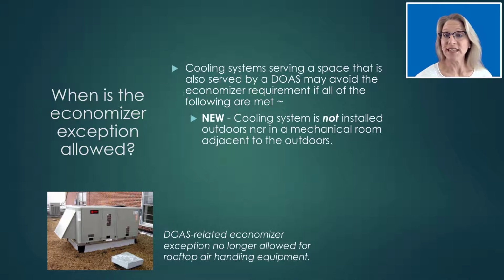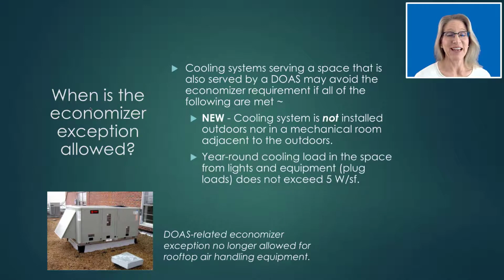The 2015 WSEC allows this exception to be applied to packaged rooftop units. However, this doesn't make much sense for air handling equipment that is installed outdoors or adjacent to the outdoors and thus can be readily provided with economizer. So this allowance has been removed in the 2018 WSEC. And the original requirement for this exception has not changed.